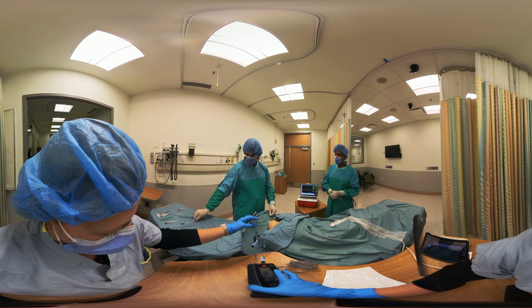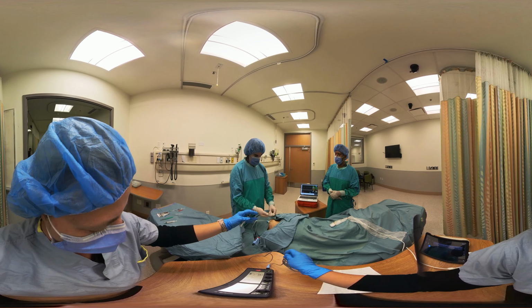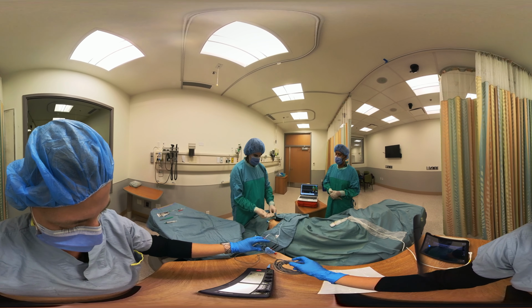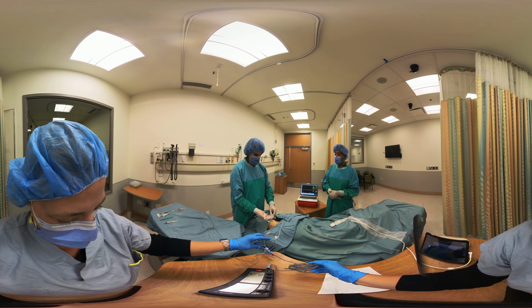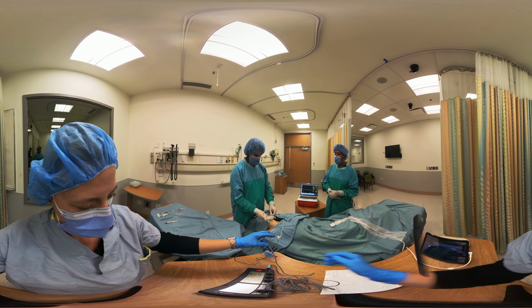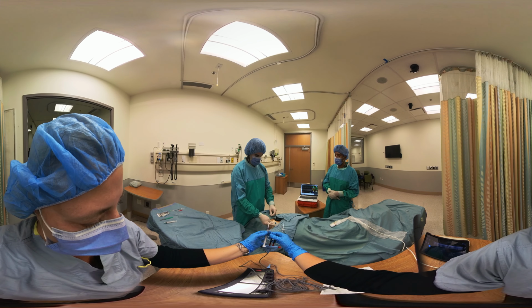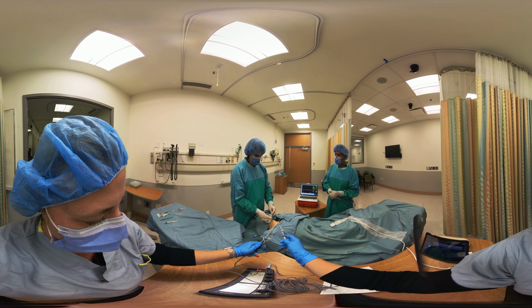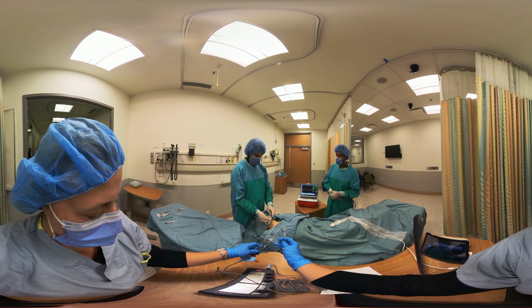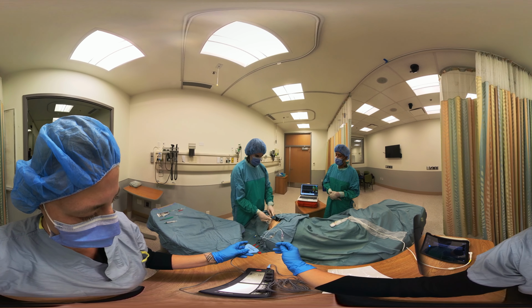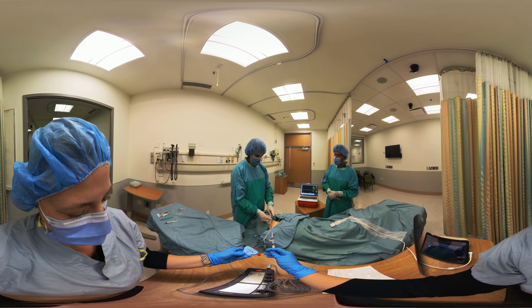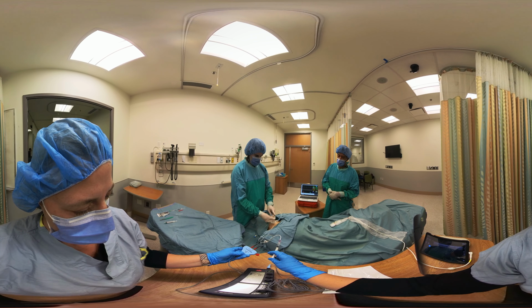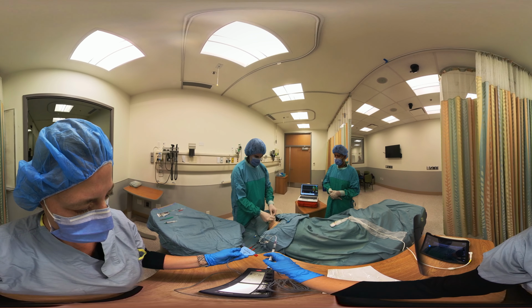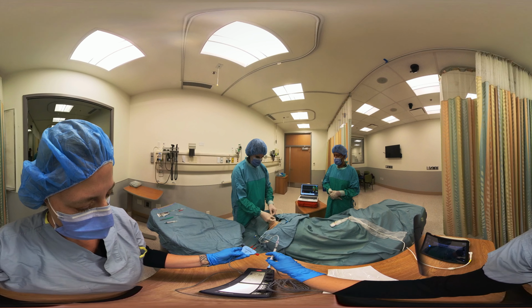What they will first do is put the sheath over the catheter, which will make sure that it is sterile. It is very important to put the sheath in the correct direction. This is a common area of mistake during catheter insertions. You want to have the portion of the sheath that actually attaches to the cordis going in the direction away from the pacemaker. So I'll get you to insert that.